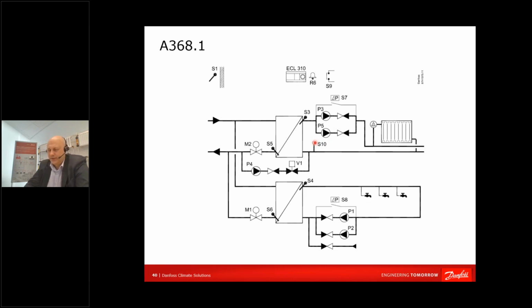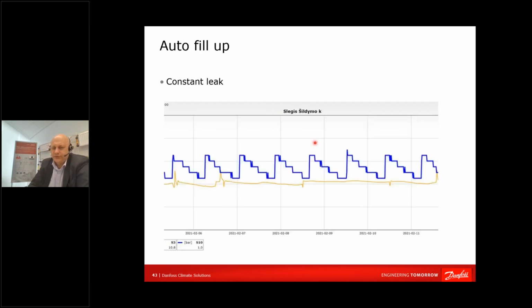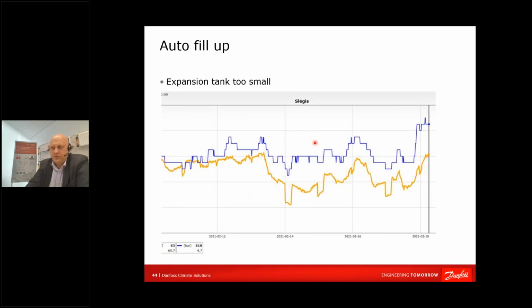Oh, that's a tricky question. Okay, first of all, I would advise using a pressure sensor, because you can have control of the system and you will discover what is happening. A pressure switch just has a function that it will either switch on or switch off. So you will not be aware of what is happening with the pressure in the system. You will just be able to discover it's on or it's off. So it's less informative. I would advocate for the pressure sensor just because of the information.